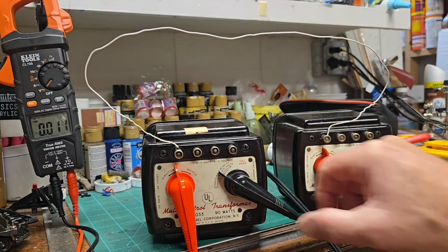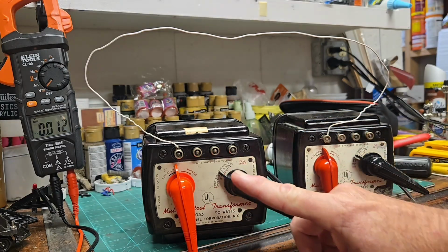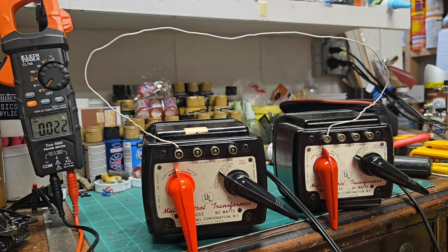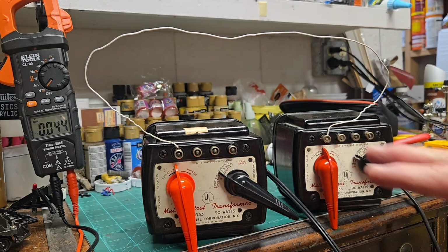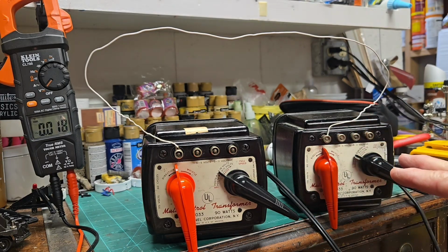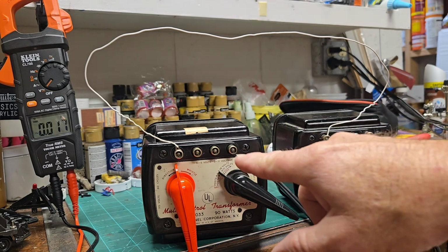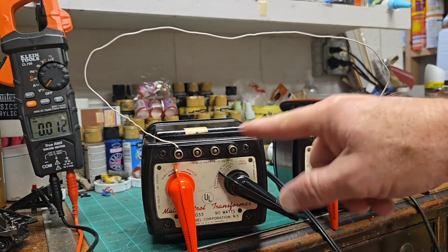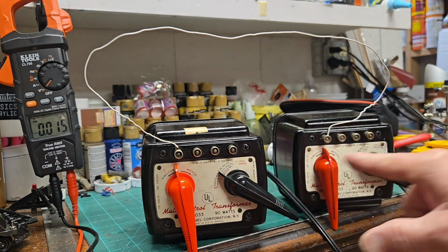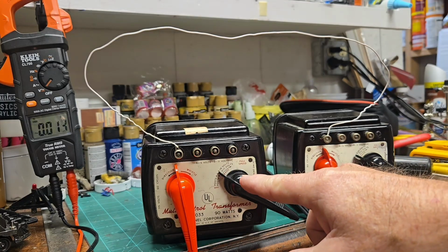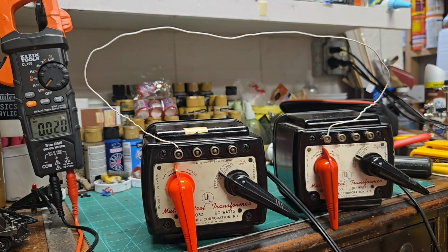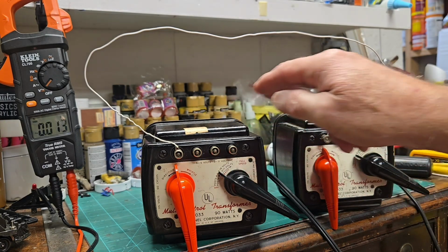So what I did is dial both transformers to approximately 8 volts. It's hard to get them exact, but for demonstration purposes this is easier to show, because if these transformers are in phase - and there's no way to know until you test them like this - the reading I'd expect to get would be close to 0, since my settings are 8 volts. So it's safe to say 16 volts and 0.